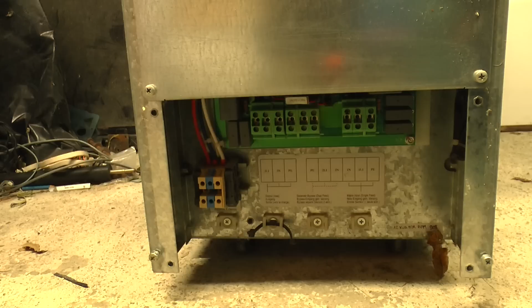The left hand one is used, it's got these skinny little wires in here, you can barely see. You see this red one here, just for monitoring the status of this breaker. And mains input live, besides dropping straight onto the board, goes up to the maintenance bypass breaker, and the input neutral goes through this CT down to this panel here, and then it goes up to the right hand fuse and the right hand pole of the output isolator. So the neutral is coupled straight through. There's not much else to see on the back. The two 24-volt fans just blow air through this large heatsink, which goes the full length of the panel, and we've also got vents here as well.